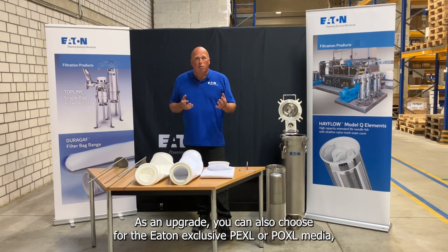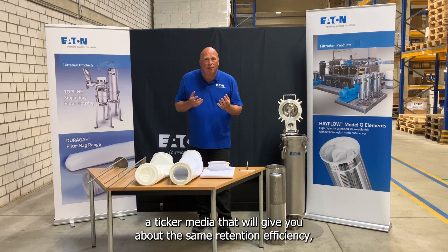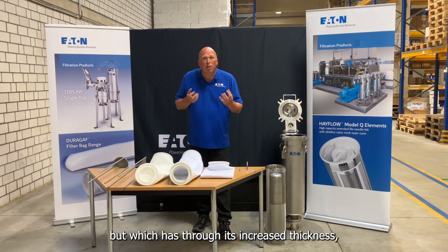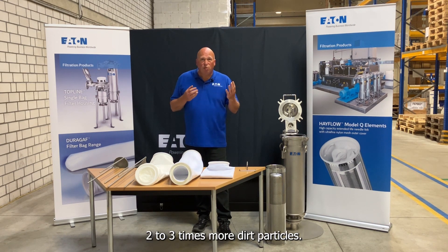As an upgrade you can also choose for the Eaton exclusive PEXL or POXL media, a thicker media that will give you about the same retention efficiency, but which has through its increased thickness a lot more pore volume, and as such can hold two to three times more dirt particles.